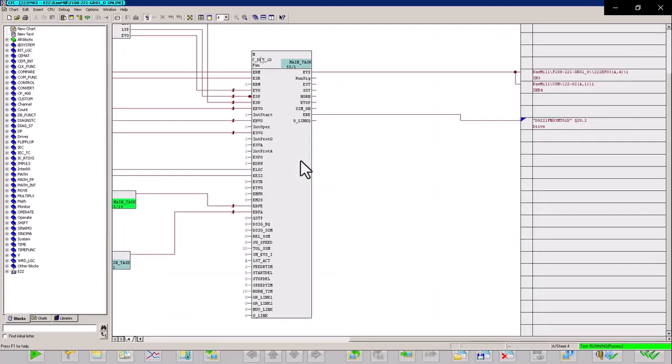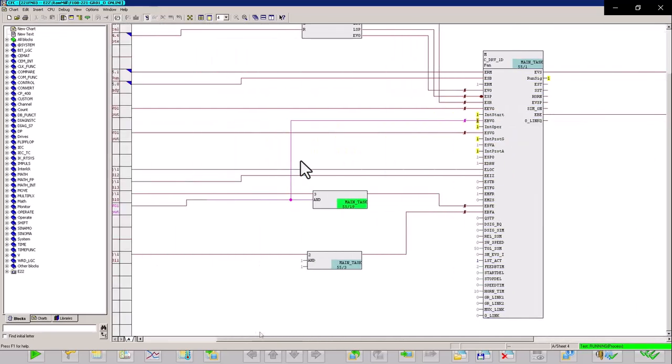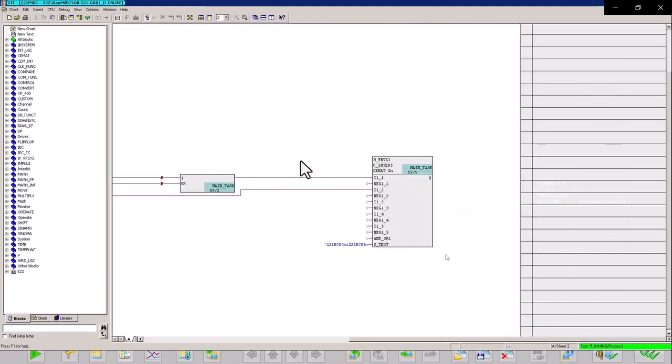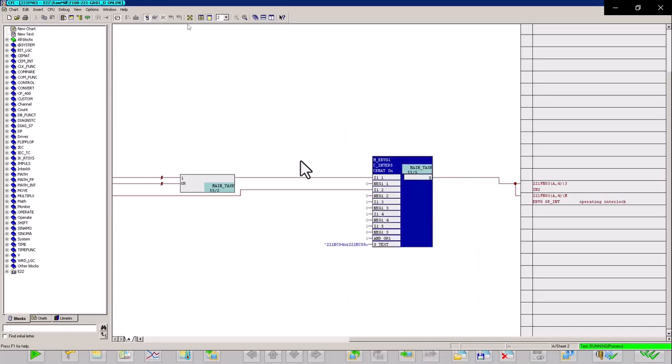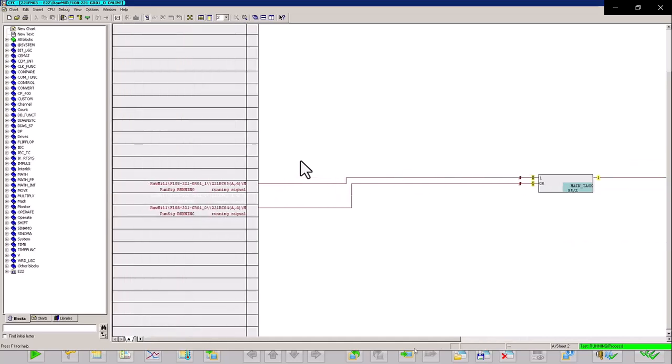The drive block of the 221FN03 is watched online, and in the interface of the operation interlock, you can see the interconnection, and over here we have a number of signals that are being fed into the operation interlock input interface of the 221FN03. Two signals have been ORed, while the third signal is ANDed with the output of the two ORed signals.